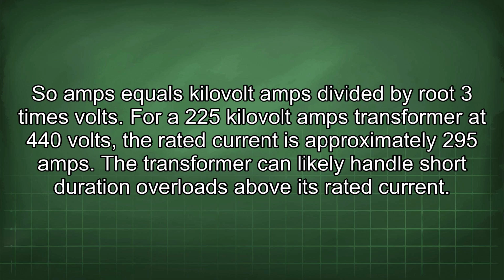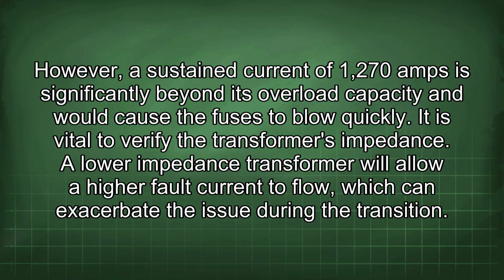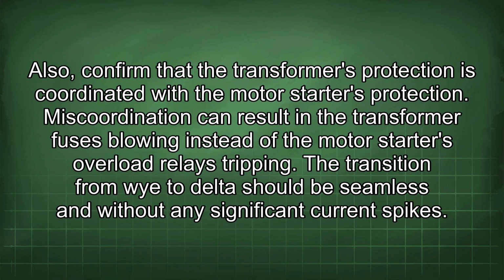The transformer can likely handle short duration overloads above its rated current. However, a sustained current of 1270 amps is significantly beyond its overload capacity and would cause the fuses to blow quickly. It is vital to verify the transformer's impedance. A lower impedance transformer will allow a higher fault current to flow, which can exacerbate the issue during the transition. Also, confirm that the transformer's protection is coordinated with the motor starter's protection. Miscoordination can result in the transformer fuses blowing instead of the motor starter's overload relays tripping.